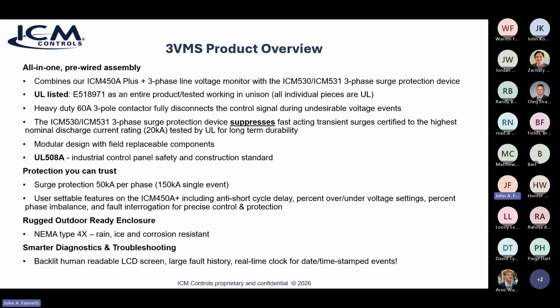So this is a modular design with field replaceable parts, another great benefit for this product. Some of the other products you might know, like the 493, you kind of have to replace the whole product. But with this one, you can replace individual pieces inside of it. It's protection you can trust, with 50,000 amps per phase up to 150,000 amps of surge current protection.